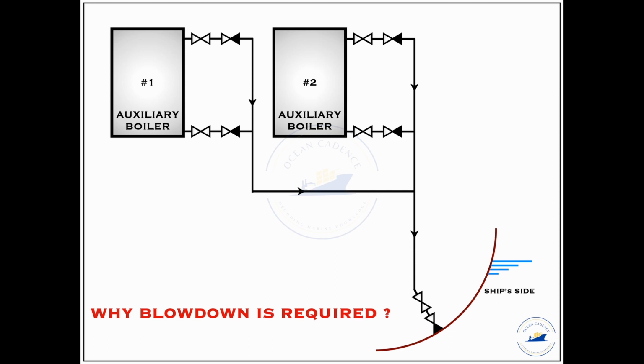So now that we have known why a boiler blowdown is required, let us now tend towards the topic, how do we carry out this blowdown? First of all, let us consider a water drum boiler. Now we know that the water is filled up to a very high level in order to maintain the equilibrium condition and to make sure that water is always available for evaporation and thereby generation of steam. So the water that is available at the top side of the drum will carry out all the lighter suspended solids as well as any oil particles or any other scum particles that are being carried over through the steam generation and the steam circulation network.